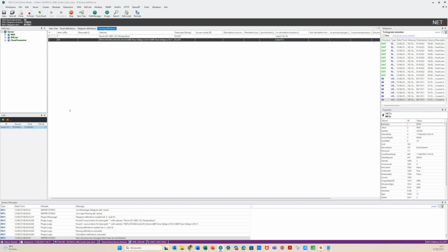Normally, we used to create a supervision visualization using icons for each individual address. So in a short view, you can see not only if one device is not good, but also which device is not good. Because what I recommend is to represent it in a page with the layout of the bus cable and using icons that can be green, for example, and fixed when it's okay, and red flashing when it's not okay. So you can identify very fast which device is not working fine.